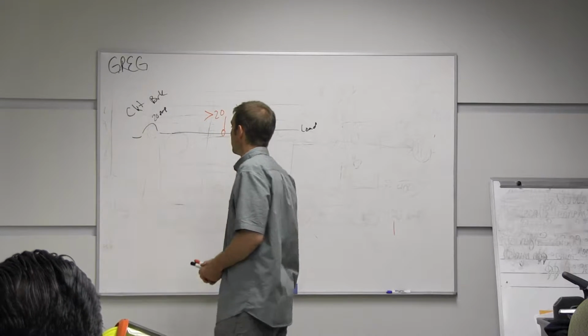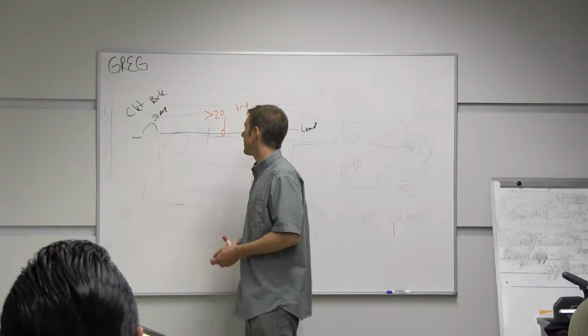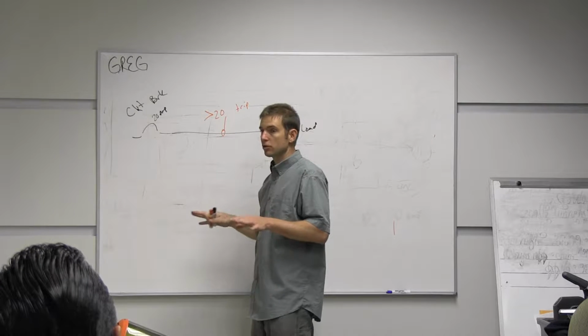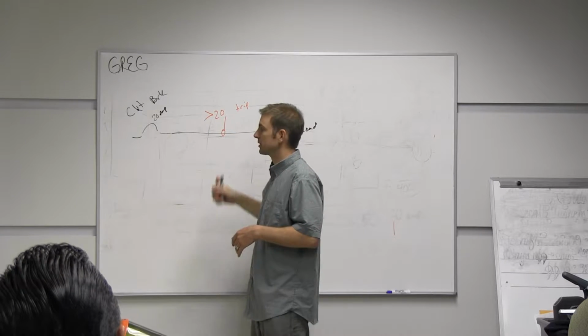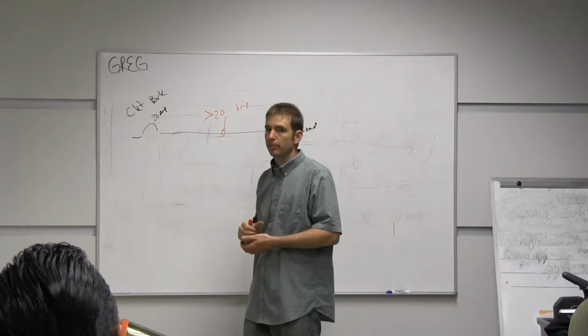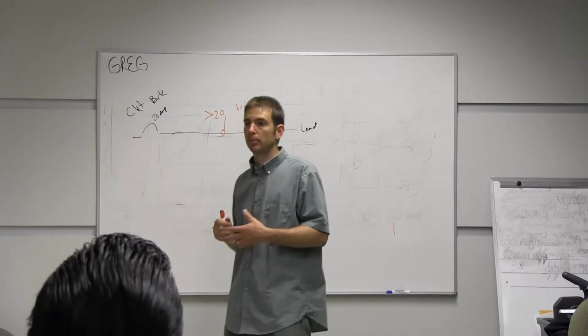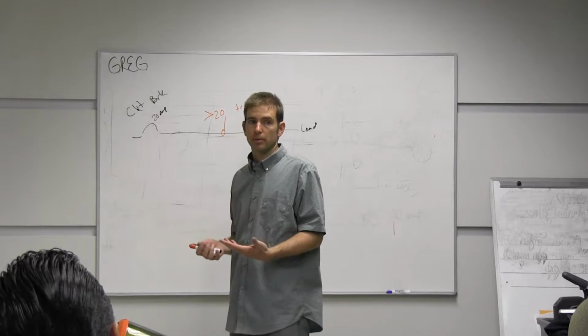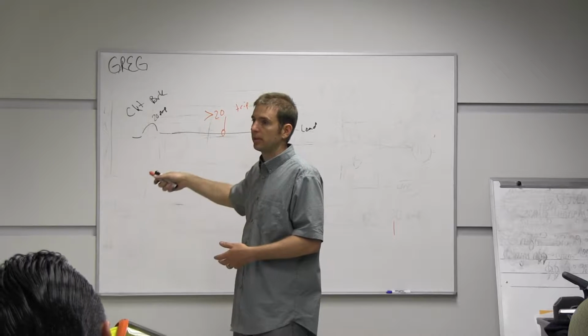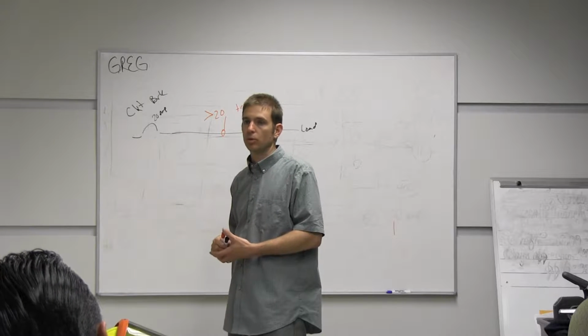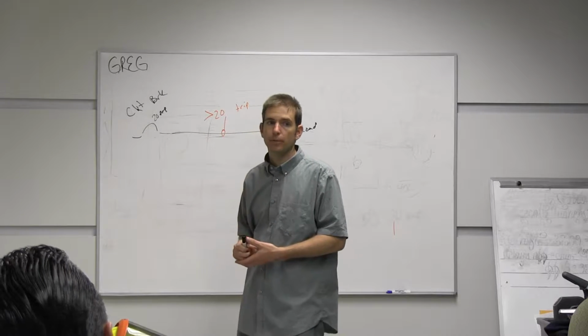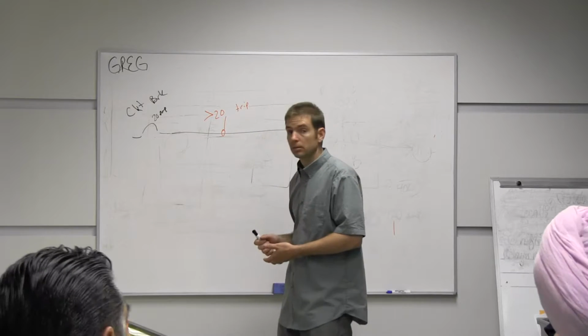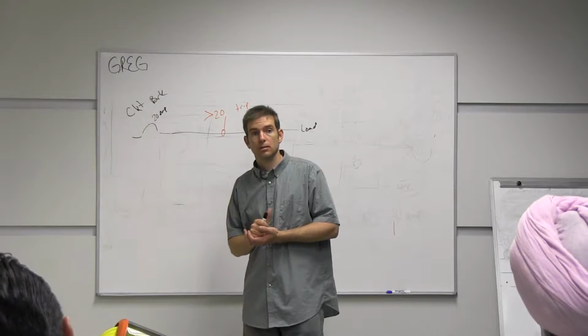Circuit breakers: if the current is less than 20 amps, it shouldn't trip. If it's more than 20 amps, it should. Historically, there have been some breaker manufacturers that made a breaker that doesn't trip. You could put 40 amps on a 20 amp breaker and it just gets warm, like you can test with your infrared tester. So what is the protection there, if they don't trip?